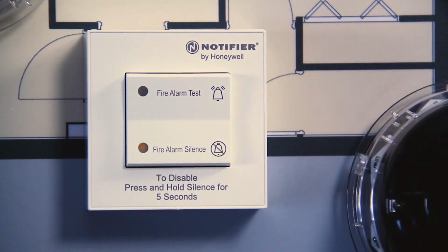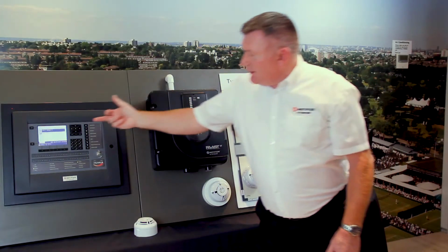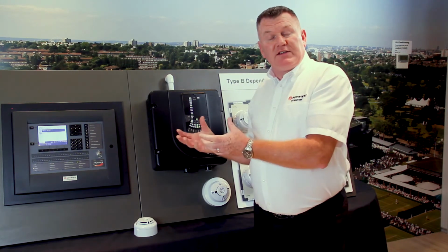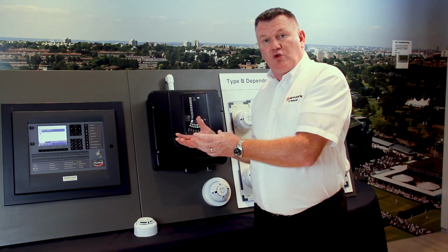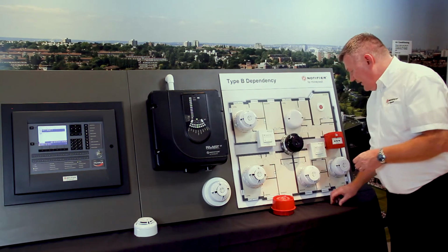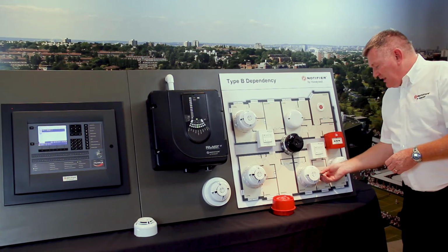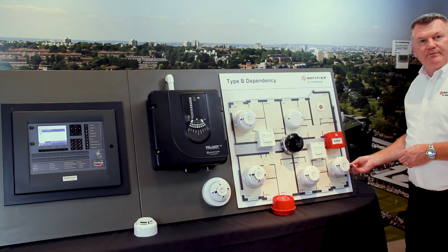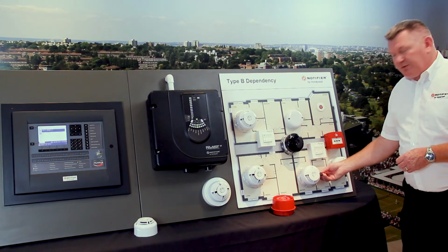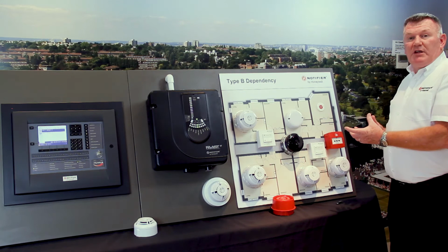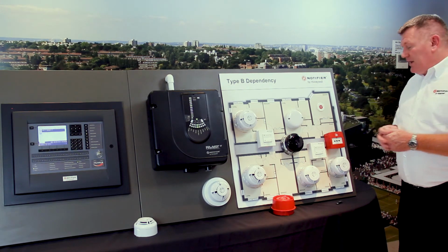the LED is enabled on the button, and if I move across to the fire control panel, you'll see that it brings me through the detectors that have been disabled. Those devices are obviously entered into the fire control panel log. If I come back to the panel now and use my magnet, these detectors won't go into alarm condition. At the end of the 5-minute period, as I said before, the system will automatically re-enable those devices and they are now back into the system.